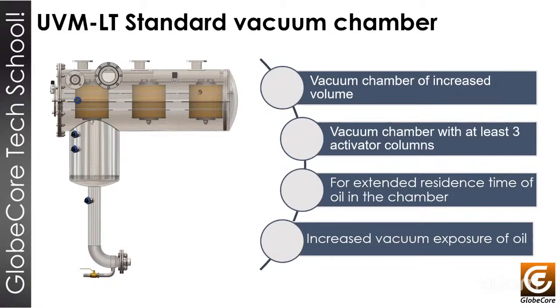The thing will be really easy. The flow of the oil will go inside this pipe, and the oil will have 3 different routes to go inside the vacuum chamber. The oil, that means the complete flow, will divide in 3. That increases by 3 the time the oil remains inside the vacuum chamber. Then the oil is exposed to the vacuum. The oil will fall down in the vacuum chamber, and all the 3 flows will go together to the outlet of the machine. And that means the oil was exposed to the vacuum 3 times.